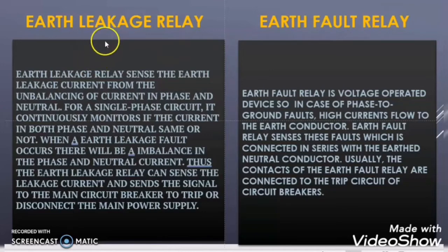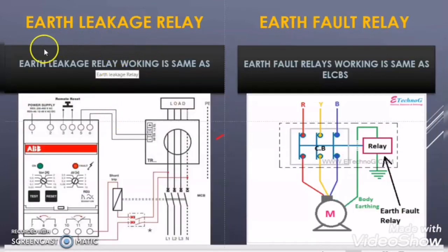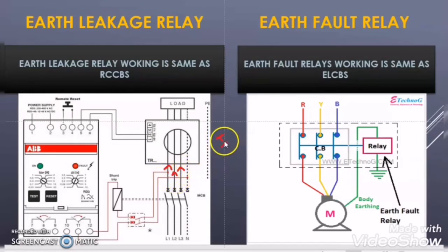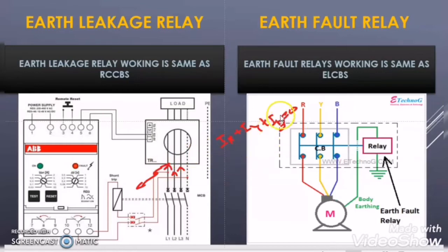Let us understand the working principle of both. For the earth leakage relay: at normal healthy condition, some current flows through R, Y, and B phases. The phasor sum IR + IY + IB is always zero in healthy condition. But if a fault happens in one phase, the phasor sum will not be zero, which activates the CBCT — the core balance current transformer — and the CBCT gives feedback to the earth leakage relay to trip the circuit.